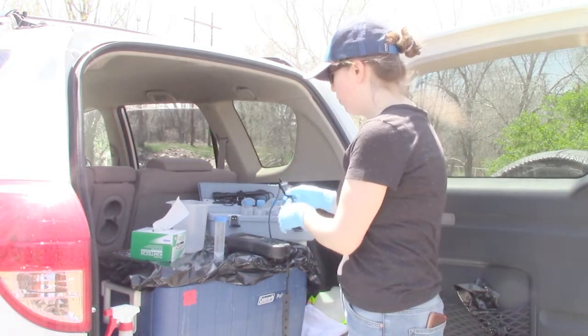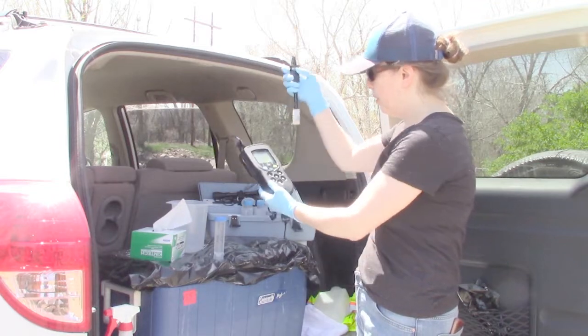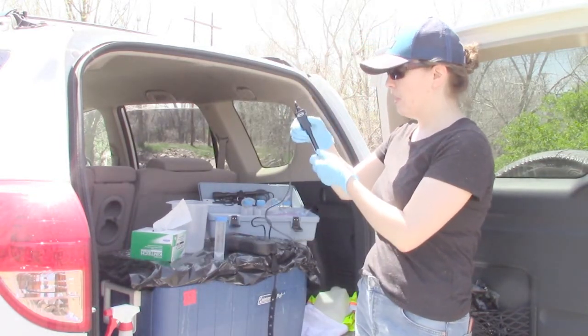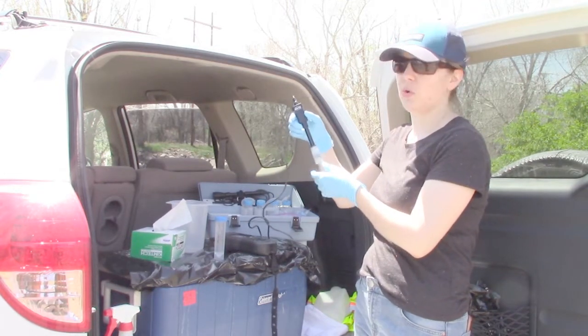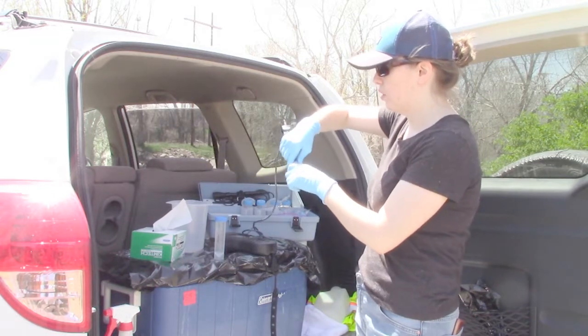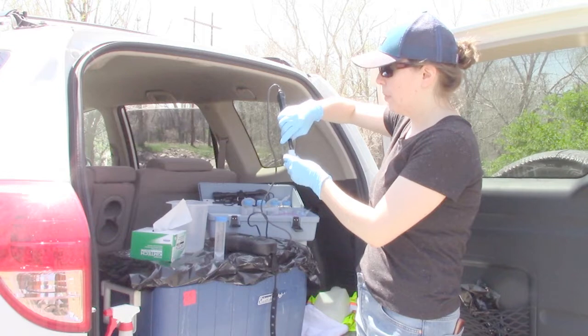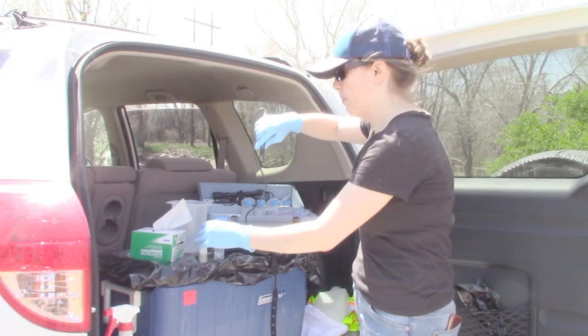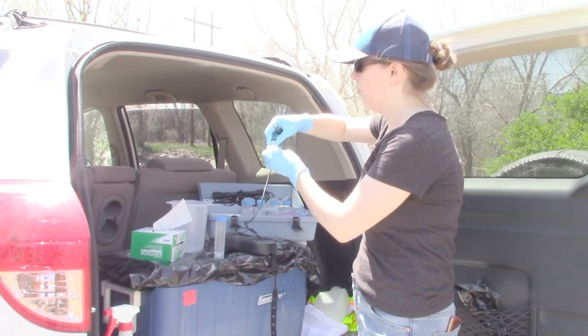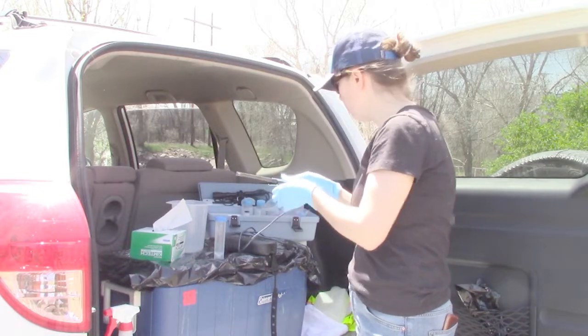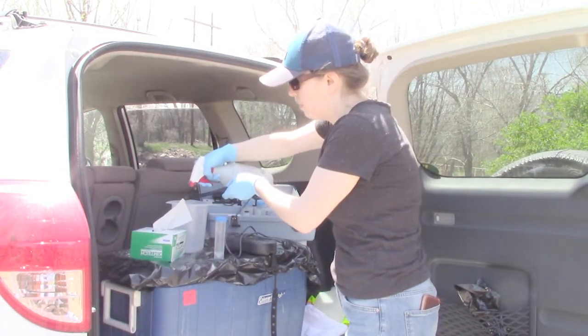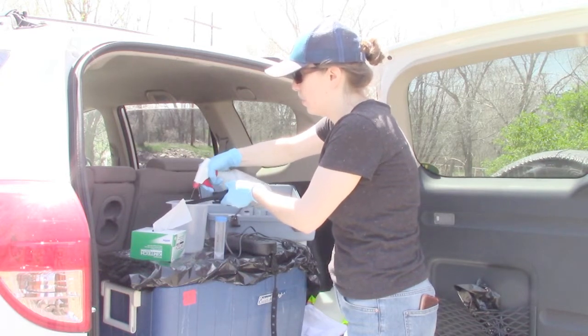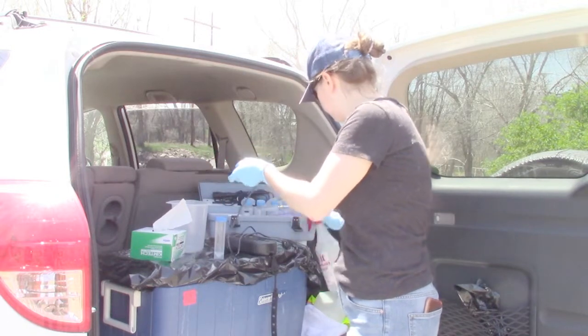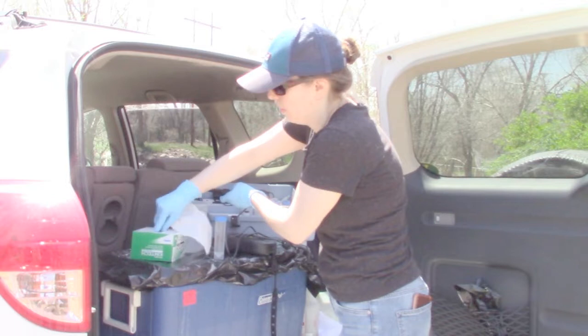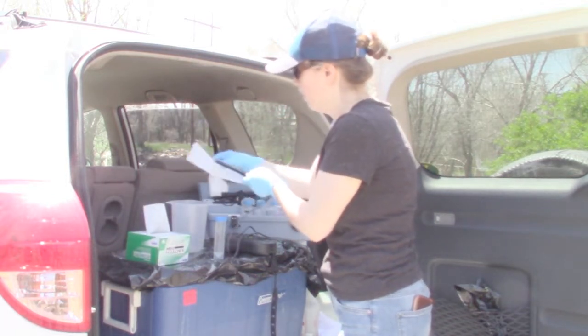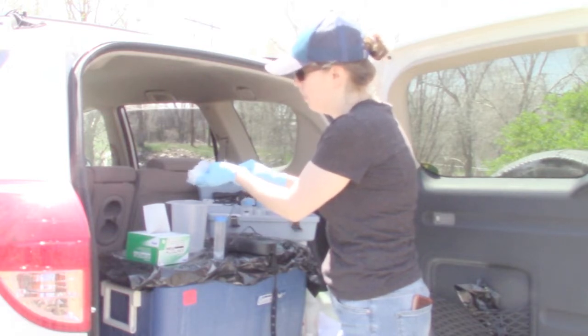conductivity. So the first thing you want to do, you take out the multimeter, then you connect the probe. In this case, we're going to start with the pH probe. The important thing about the pH probe is that it has to be stored in a storage solution, so it should never dry out. So you unscrew this little bottle, take the cap off, and put it somewhere where it doesn't fall. Then always rinse the probe with water between storage and a new sample or calibration, and then blot it dry with a Kim wipe.